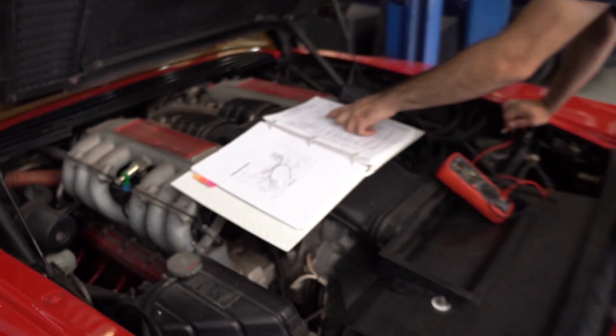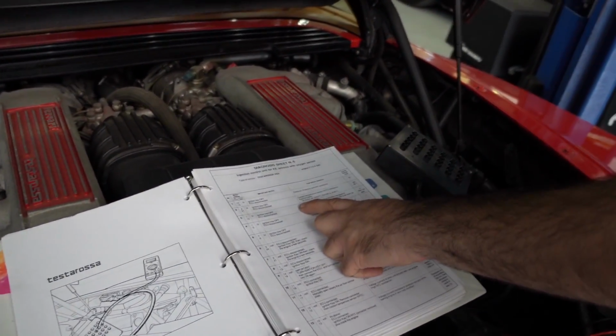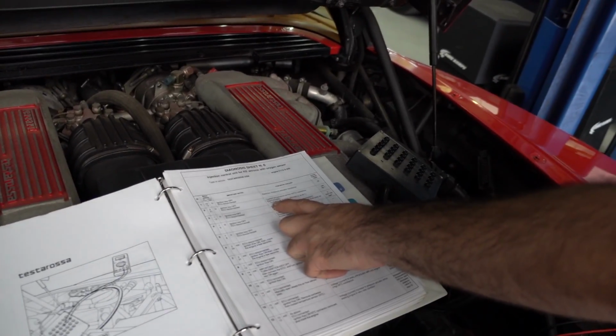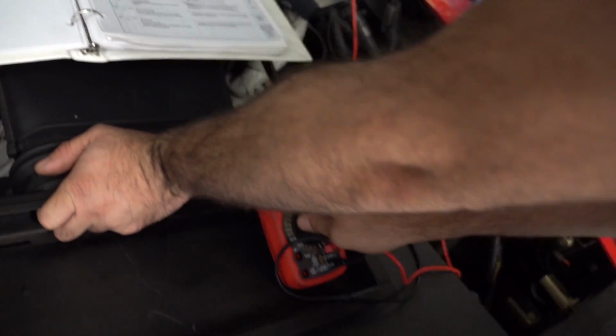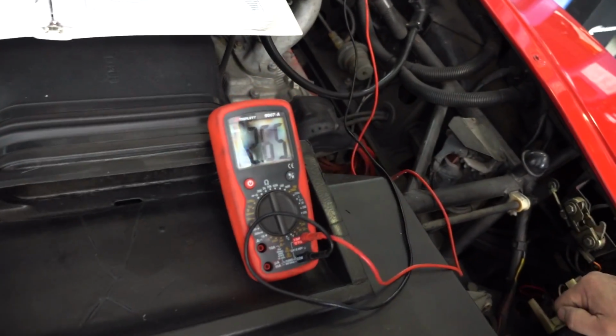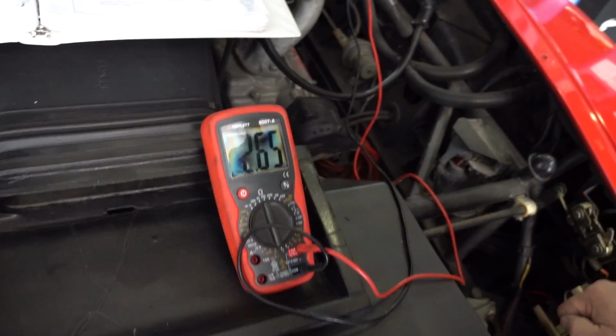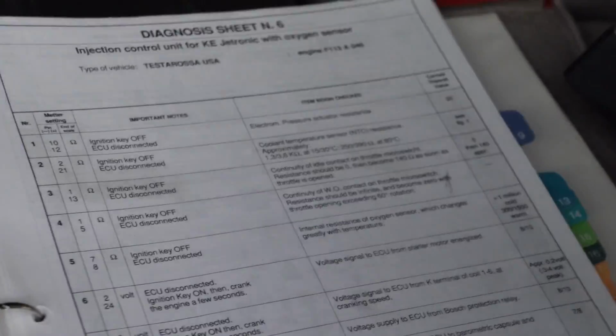It says at 15 to 30 degrees Celsius, we should be in the 1.3 to 3.6 K ohm window. We're reading 221, and we need to go to the 20K range. We're at 2.65, which is right in the middle — I'd say that's pretty acceptable.